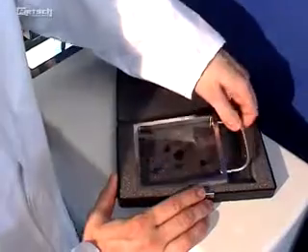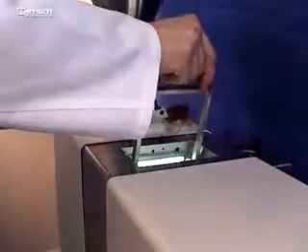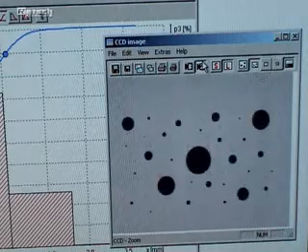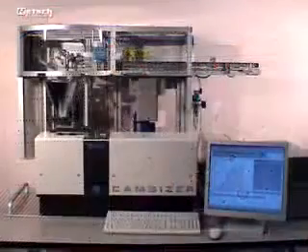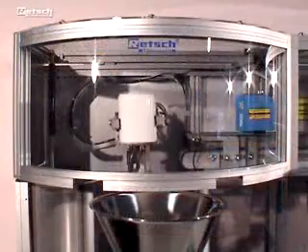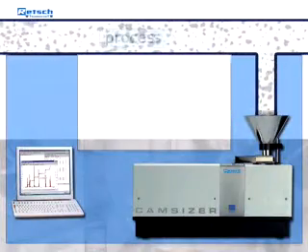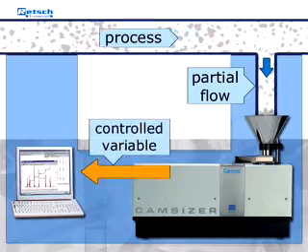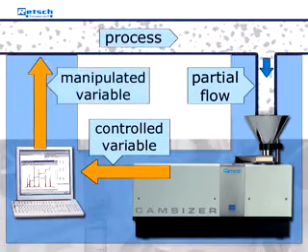Using a highly accurate and certified reference object, the Camsizer can be recalibrated and automatically adjusted within seconds at any time. The constantly increasing trend towards laboratory automation in particle size analysis can be realized by an auto-sampler system. Based on a kind of trend analysis, the process parameters can be optimized through a closed-loop control circuit.